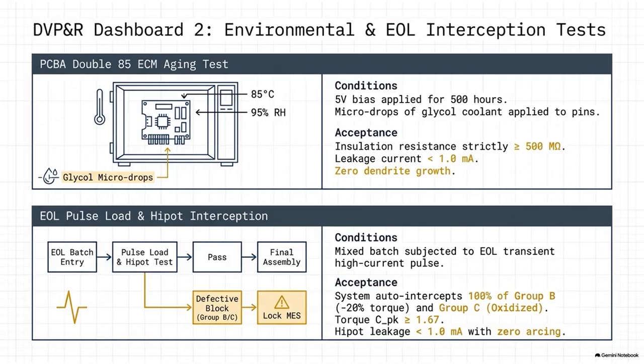All three groups are anonymously routed down the production line to the final end-of-line, or EOL, test station. As the packs initiate their boot sequence, the EOL testing rig fires a massive, localized step current pulse load through the architecture. And the pass criteria? The automated EOL system has to successfully differentiate the sabotaged packs from the golden pack based purely on the transient electrical response. The requirement is absolute. The automated EOL system must 100% intercept every single pack from Group B and Group C.